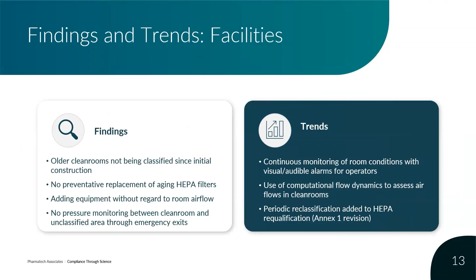This is primarily in regards to some of the revision done to the EU Annex 1, which addresses periodic reclassification for the HEPAs. Typically, reclassification had always been done for things like HEPA integrity, differential flow, differential pressure flow, and air changes. But now the Annex 1 revision is saying requalification includes reclassification according to the ISO. That effectively means the ISO requires you to grid the room out in a particular way and bring in portable particle counters to make specific measurements to assure those spaces still meet the ISO requirement or the specific requirements in the EU Annex 1.